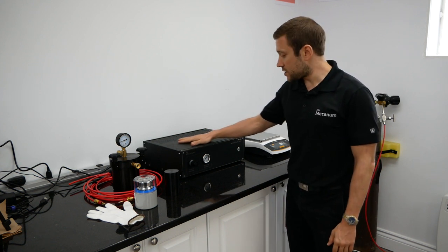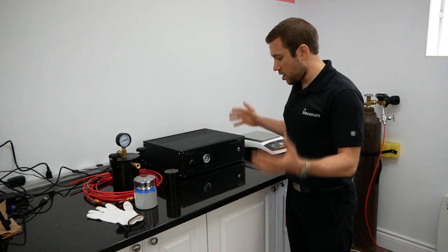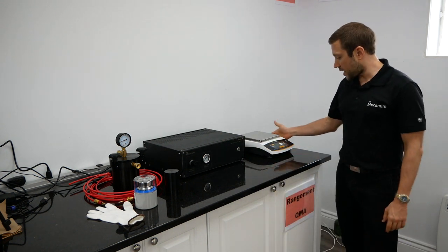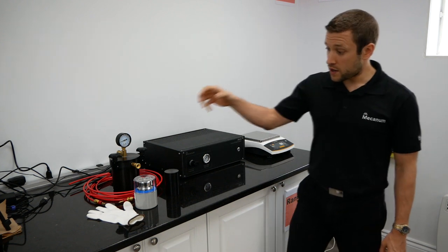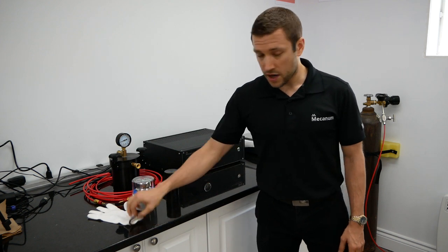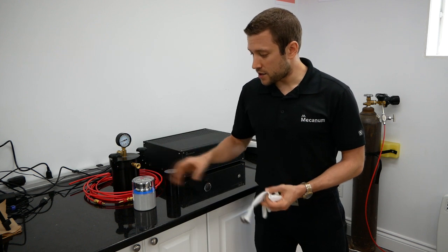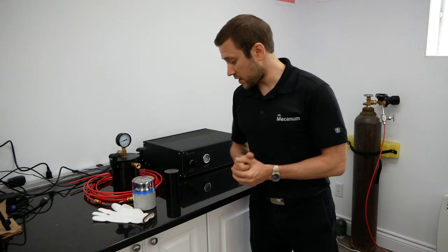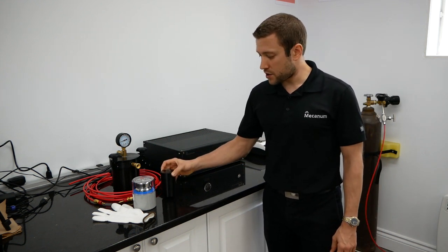So now let's see what you will get when you order a porosity meter. Of course, first you will receive the main unit. This is the unit that controls all the measurement process. You will also receive a digital scale, as well as a verification test weight, and a glove to make sure not to modify the weight of the test weight with the oil of your finger.